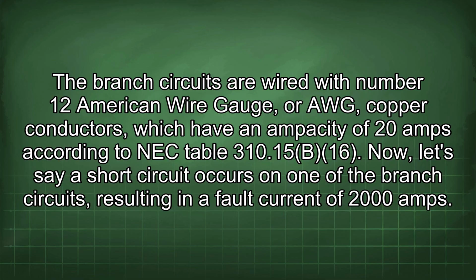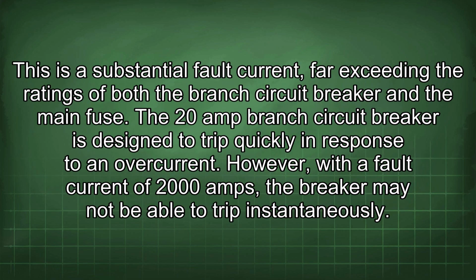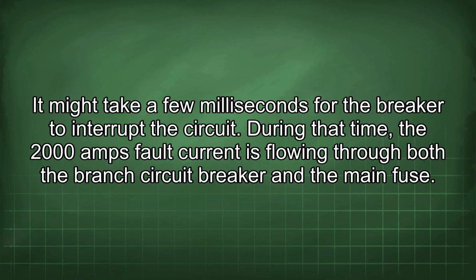Now, let's say a short circuit occurs on one of the branch circuits, resulting in a fault current of 2000 amps. This is a substantial fault current, far exceeding the ratings of both the branch circuit breaker and the main fuse. The 20 amp branch circuit breaker is designed to trip quickly in response to an overcurrent. However, with a fault current of 2000 amps, the breaker may not be able to trip instantaneously. It might take a few milliseconds for the breaker to interrupt the circuit. During that time, the 2000 amps fault current is flowing through both the branch circuit breaker and the main fuse.